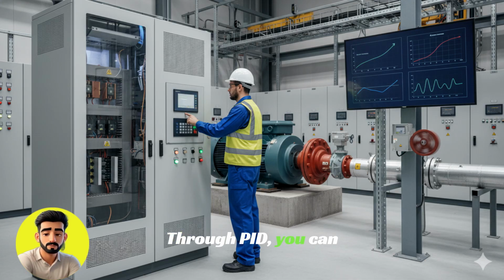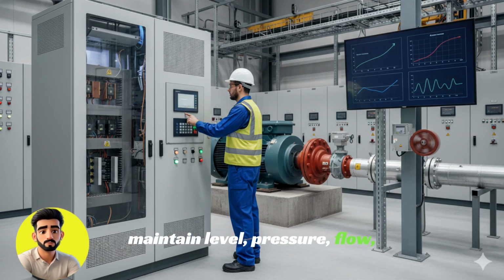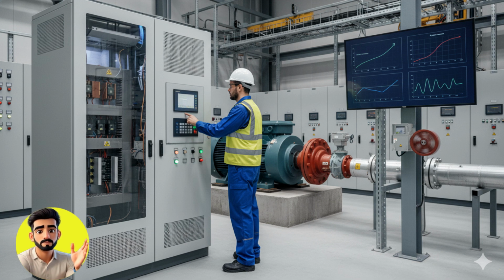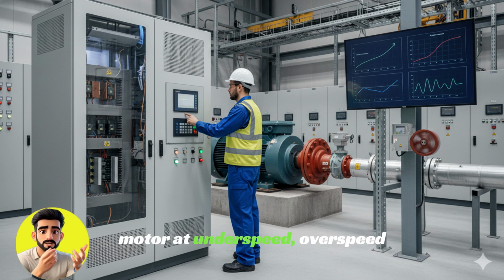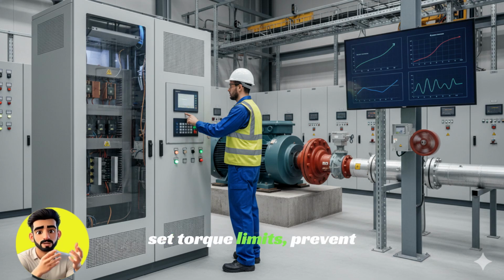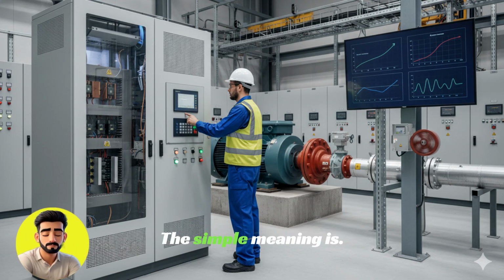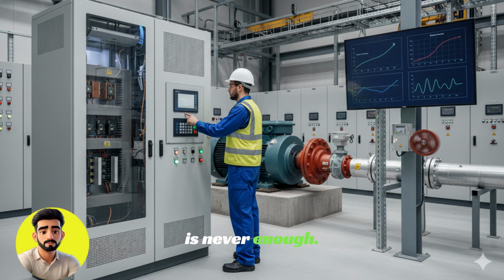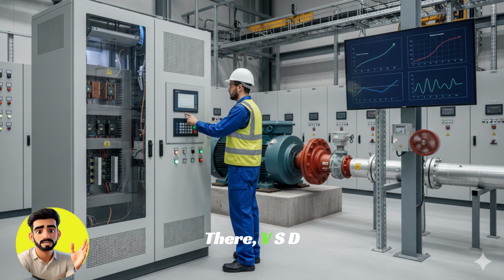Through PID, you can maintain level, pressure, flow, temperature, all. You can run the motor at underspeed, overspeed, where allowed. You can set torque limits, prevent stalls, and protect the motor according to the process load. The simple meaning is, where it is necessary to actively control the process, a soft starter is never enough. There, VSD is the real solution. There, VSD is the king.